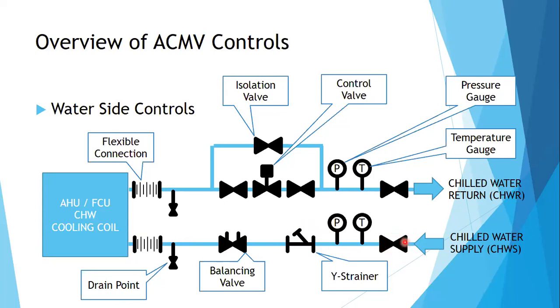Then you have your isolation valve. This isolation valve you have here is to isolate this whole system. And you also have isolation valves here. These three isolation valves are so that you can isolate your control valve. So if anything happens to this control valve, it gets faulty, it gets short, it needs to be repaired, then you have your bypass line. This coil can still be in operation even though this is being maintained or faulty, through the bypass line. And you also have your isolation valve so that you can replace this one whenever it needs to be replaced.